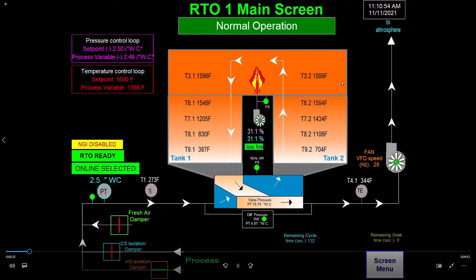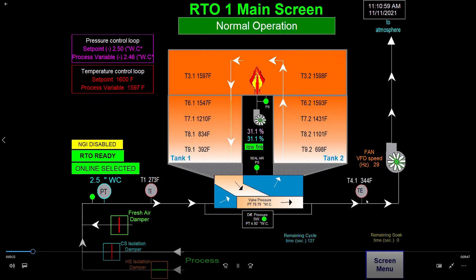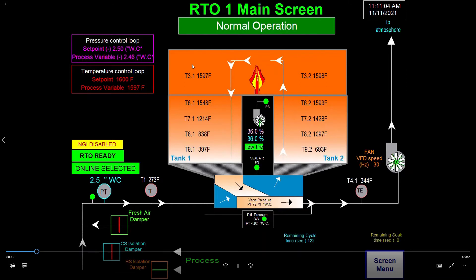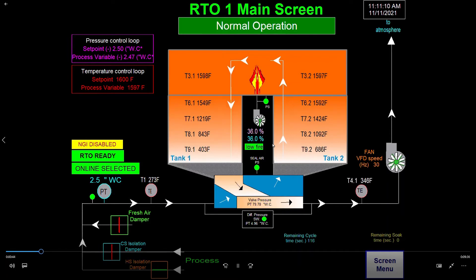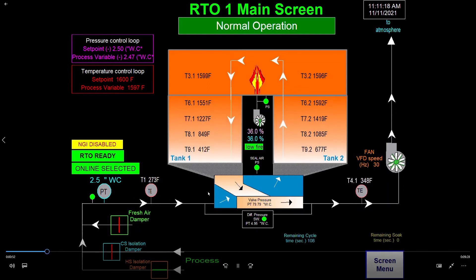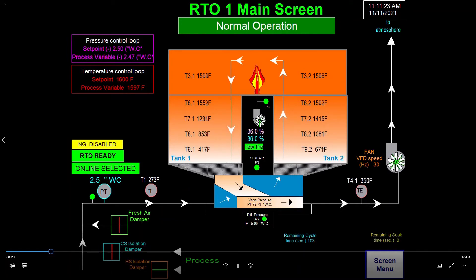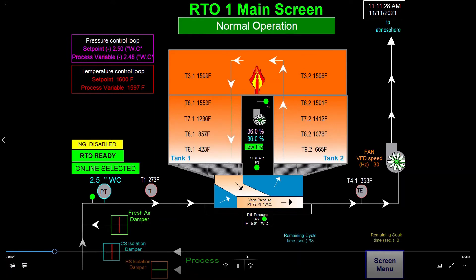This is the main body of the RTO. This is the fan and the exhaust stack that you saw in that photo. It draws air from the RTO, which consists of a combustion chamber where the VOC destruction happens, two ceramic media beds — one here and one here — that the air passes through on the way to the combustion chamber or out of the combustion chamber, a valve that changes the flow direction periodically, and the air coming in from the process. So that's where it all starts.